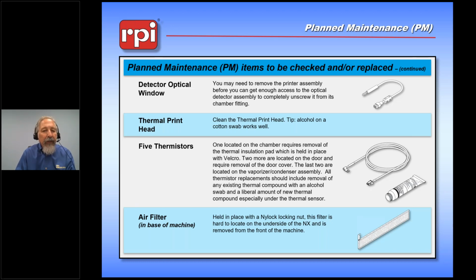If you need to get to that third window, if you want to polish it or clean it, be very careful again when removing the optical detector. It is extremely static sensitive. Make sure you do not remove that cable with the machine plugged in, and make sure that you are wearing proper static safe wrist straps to make sure that you don't damage the optical detector. There is a thermal print head. It can be cleaned. Alcohol on a swab works well.